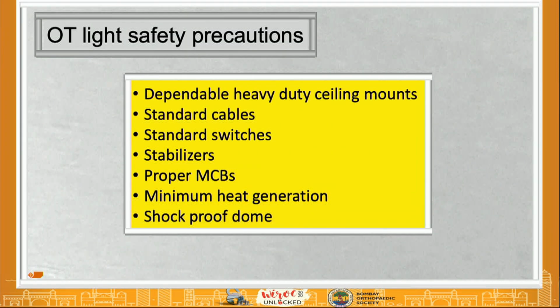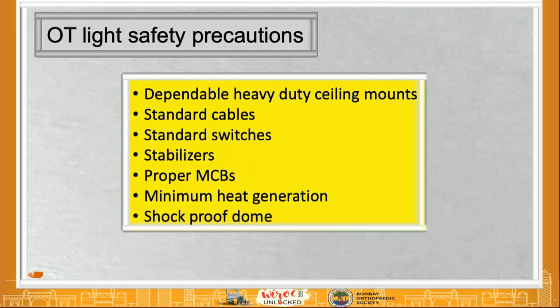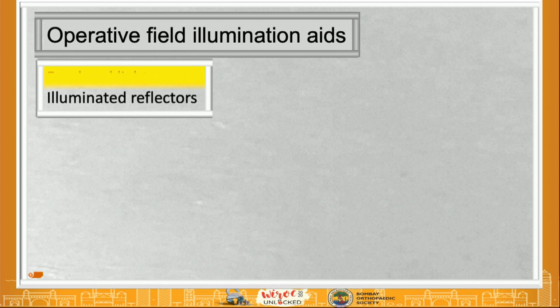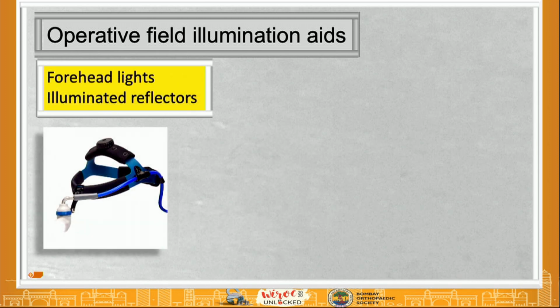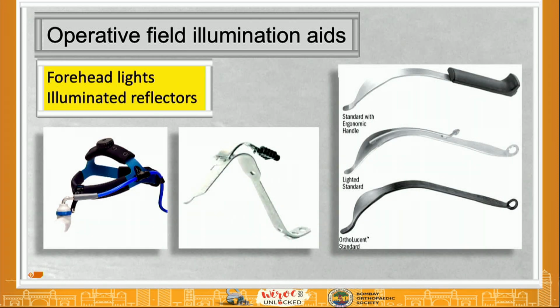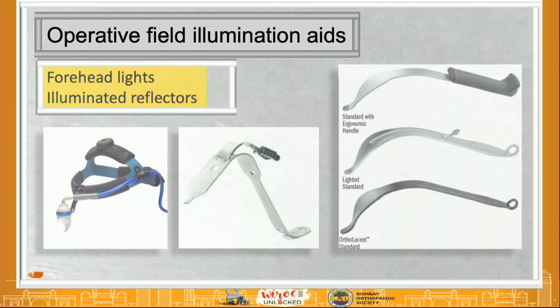So in all, you have to have safety precautions like dependable ceiling mounts, standard cables, standard switches, standard stabilizers, MCBs, and minimum heat generation, and preferably the dome should be shock proof. There are some aids like forehead lights, and there are now retractors available with the inbuilt sort of an optic fiber attachment, so you can get some light inside the depth of that cavity. These things are available.